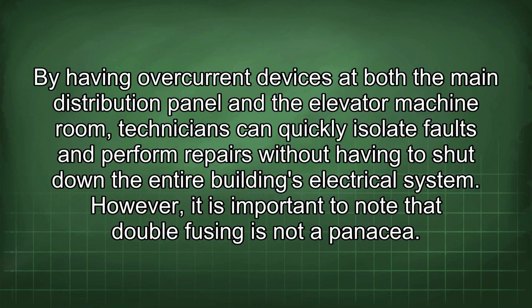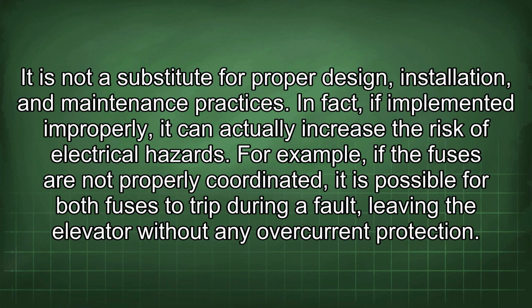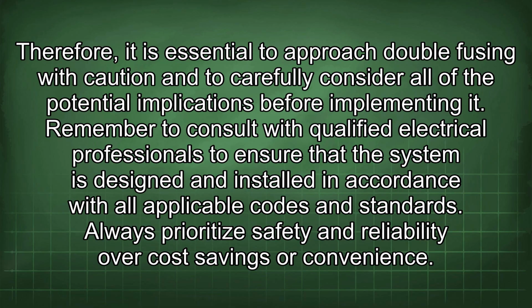However, it is important to note that double fusing is not a panacea. It is not a substitute for proper design, installation, and maintenance practices. In fact, if implemented improperly, it can actually increase the risk of electrical hazards. For example, if the fuses are not properly coordinated, it is possible for both fuses to trip during a fault, leaving the elevator without any overcurrent protection. Therefore, it is essential to approach double fusing with caution and to carefully consider all of the potential implications before implementing it. Remember to consult with qualified electrical professionals to ensure that the system is designed and installed in accordance with all applicable codes and standards.